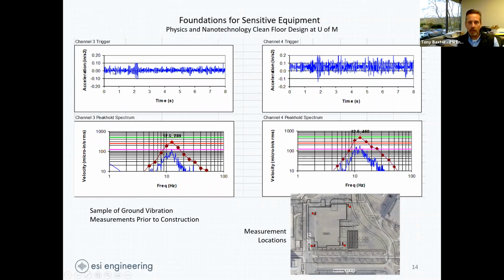Up here is the time waveform, and you can see a transient around the 2-second point. The ground vibration from traffic out here reaches almost 500 microinches per second, compared to the 125 level—so from 125 up to 500. We're quite a bit above where the lab needs to be.